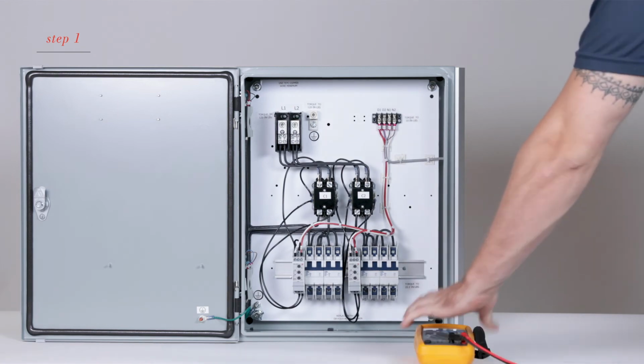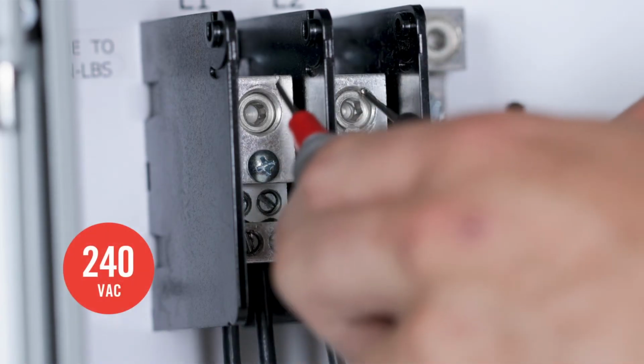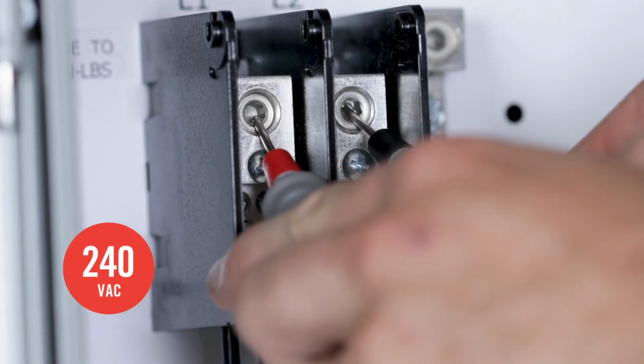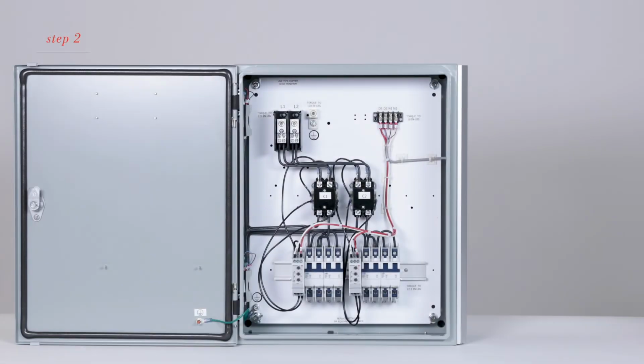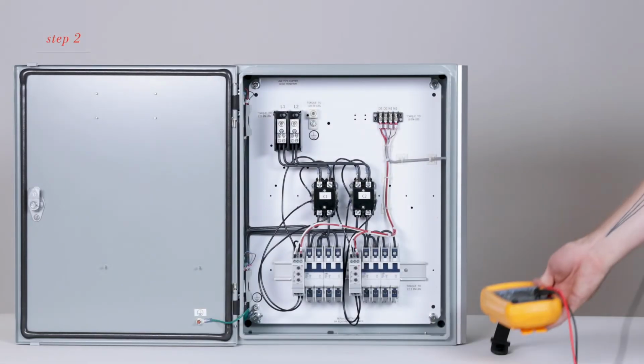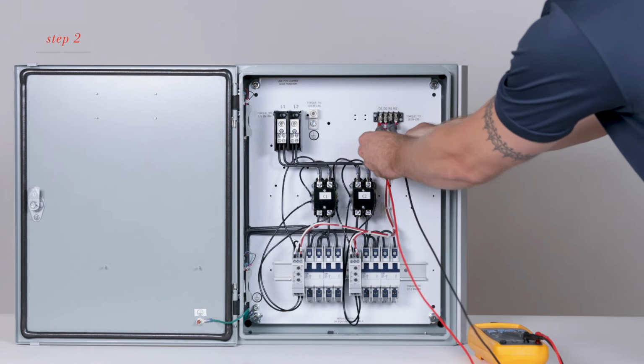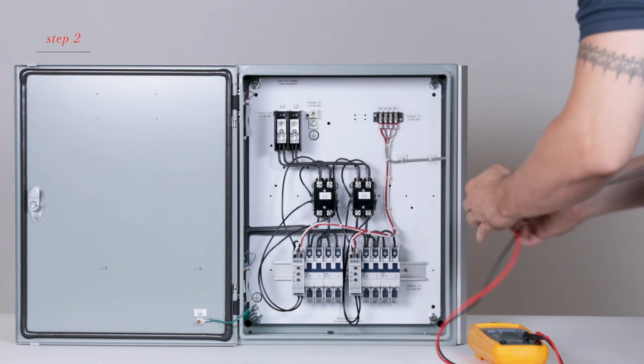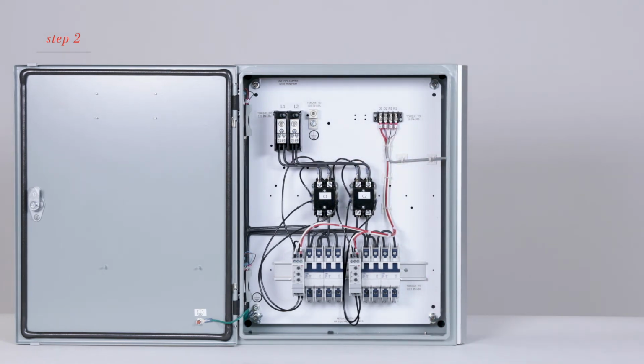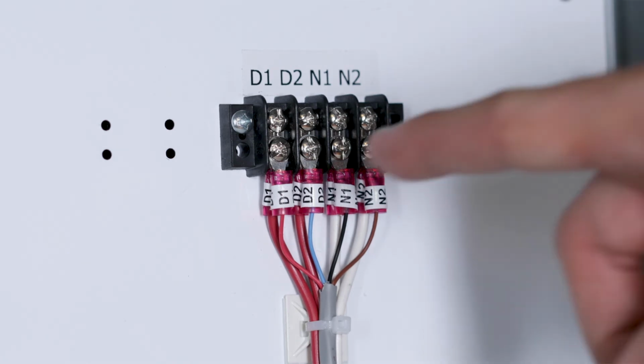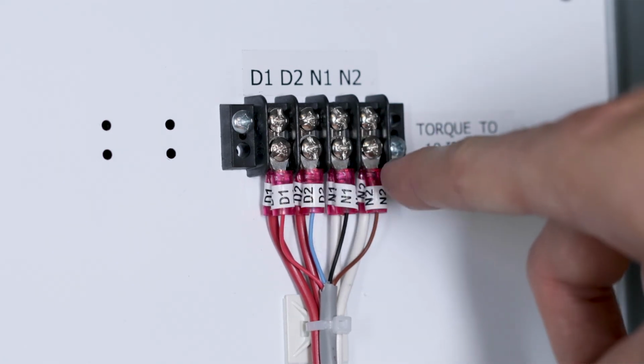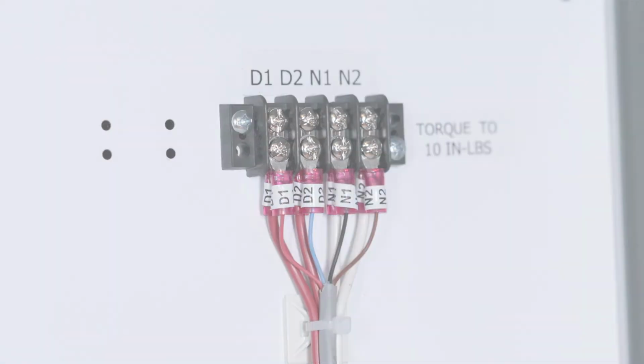Let's begin. First, check to see if there is main feed AC voltage at the distribution block. Next, is the 120 volt AC control signal present between DX and NX? You'll see this in the upper right hand corner of the control panel. Please note the X represents the universal relay number associated with the terminals.